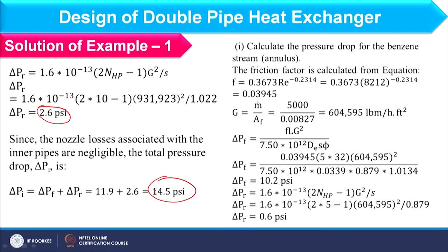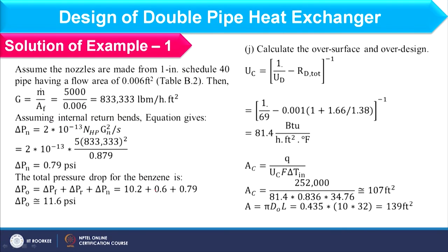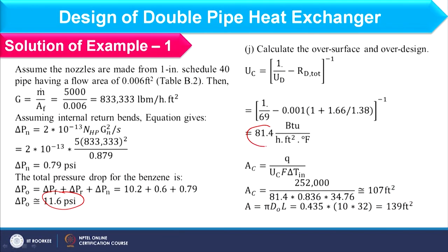So the total pressure drop in the inner pipe is 14.5, and similarly we can find out the pressure drop in the annular side, and that should be 11.6. So both pressure drops are falling in range. Now finally we have to find out how much overdesign we are considering. So for that we have to calculate the area for clean condition and for dirt condition.